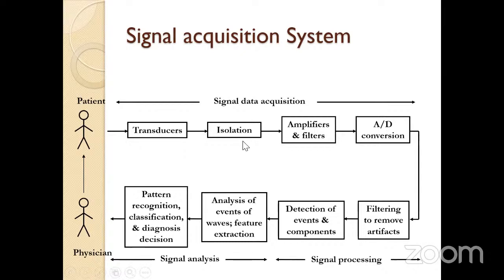Next comes the isolation amplifier, that is, the isolation circuit. Isolation circuit in the sense that this whole machine is plugged into a 230 volt supply, while acquiring a signal from the patient. So in order to prevent any shock hazards from the system to the patient, these isolation circuits have a very high input impedance, and it does not allow current flowing from the system to the patient, so that there is no risk of a current backflow or a shock. Okay, this is an isolation circuit. It doesn't allow current back to the patient. It allows it to the ground point.